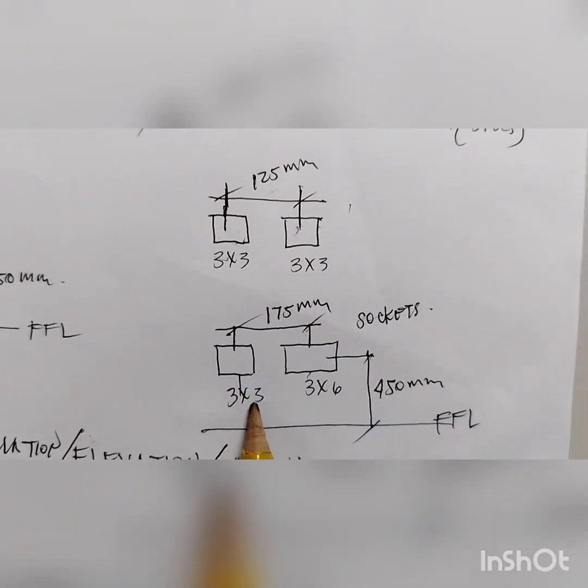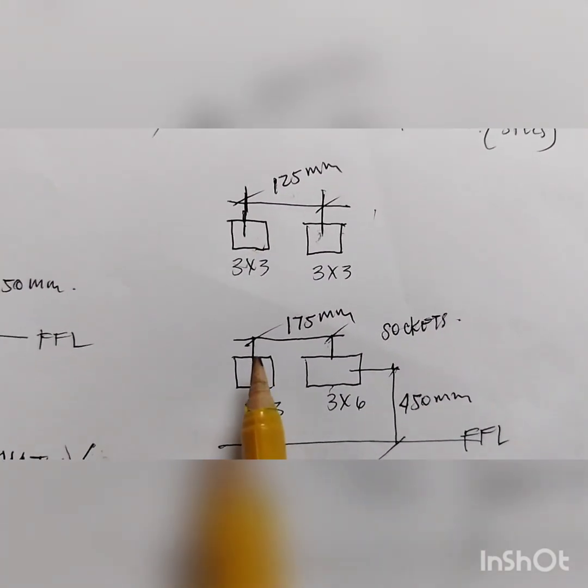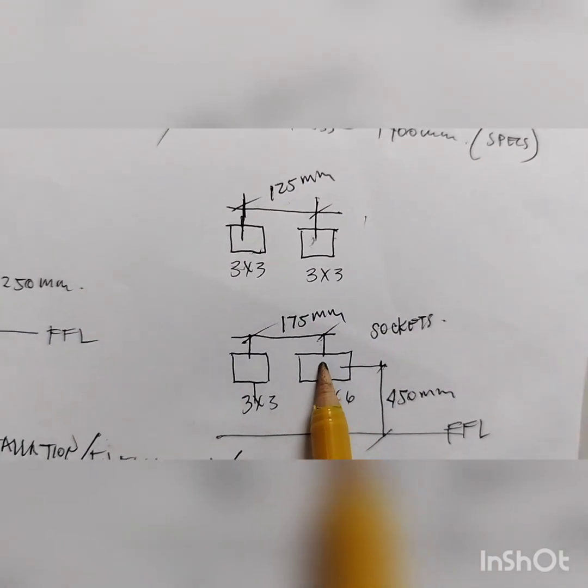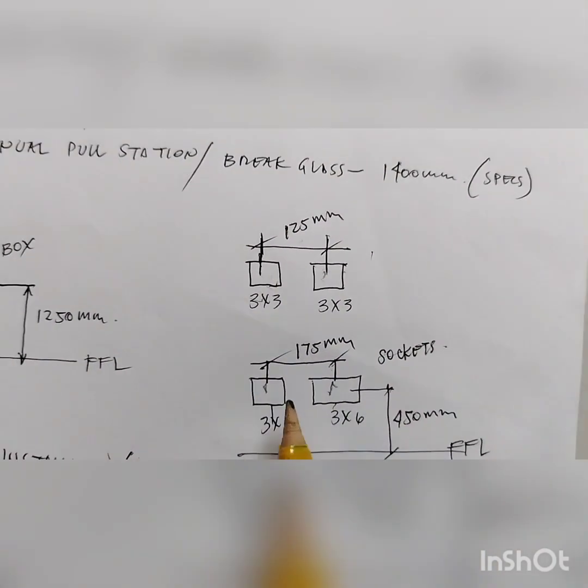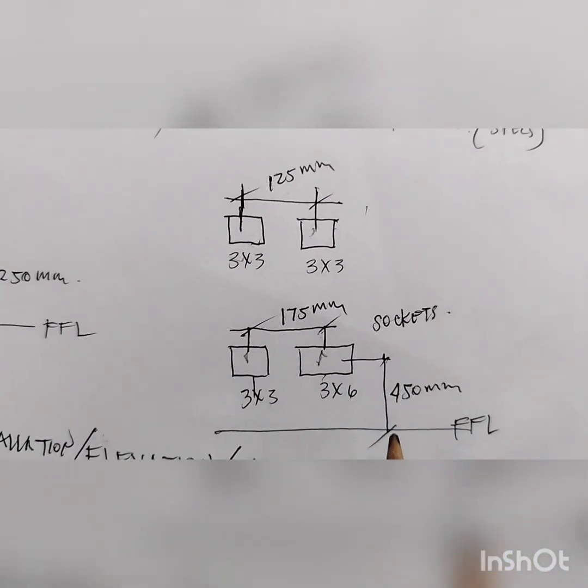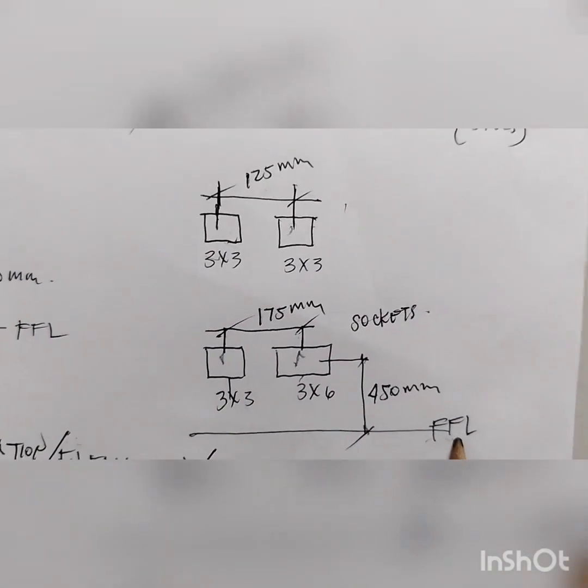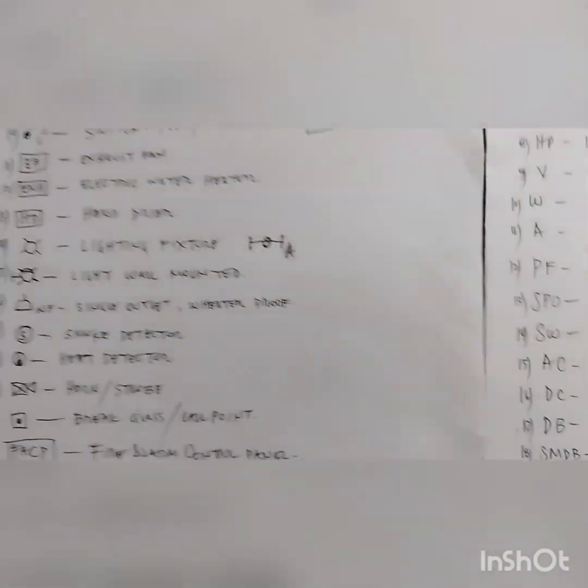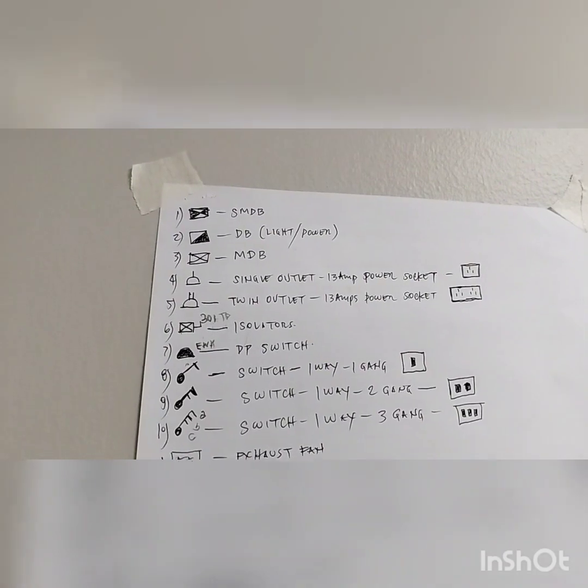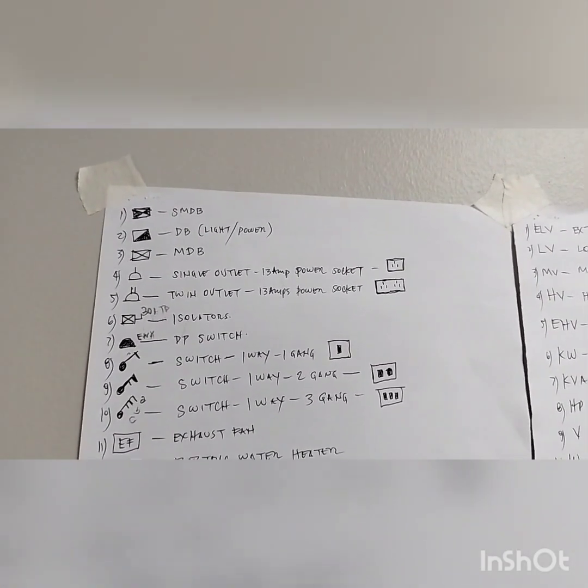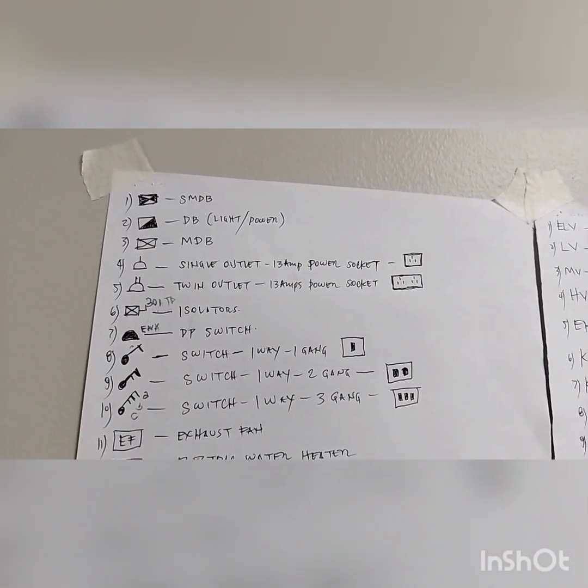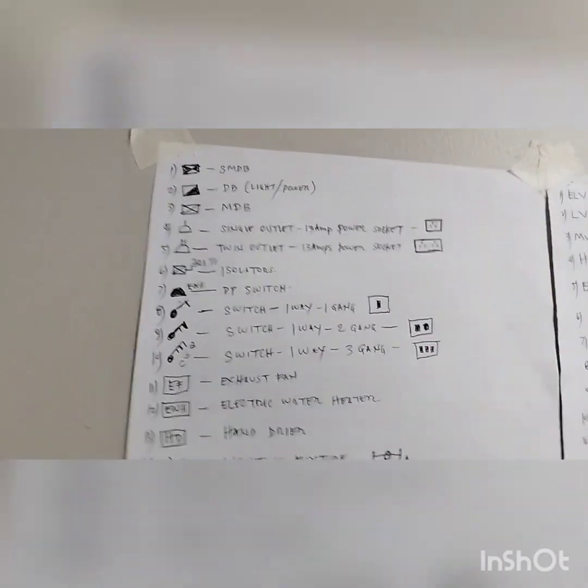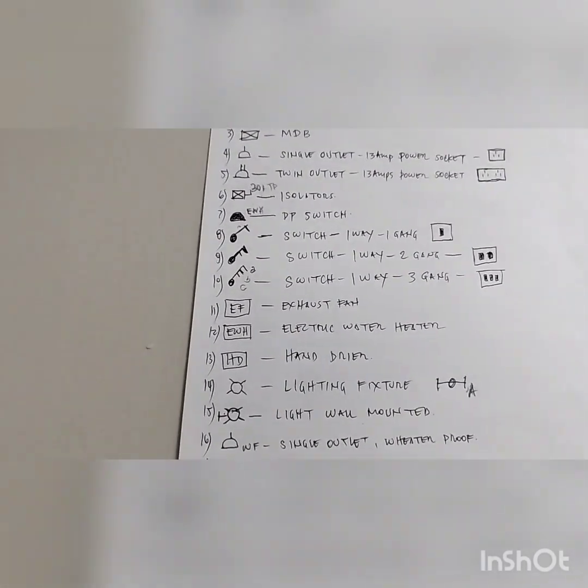If you are using one 3x3 box and one 3x6 box together, the distance between them should be 175 mm, again measured from the center of the boxes. For small power, socket, telephone, and data outlets, the standard mounting height is 450 mm from the finished floor level, measured from the center of the box. That's all for today gentlemen. I hope you learned new things and this topic added to your knowledge. Thank you very much and good luck until the next lecture.